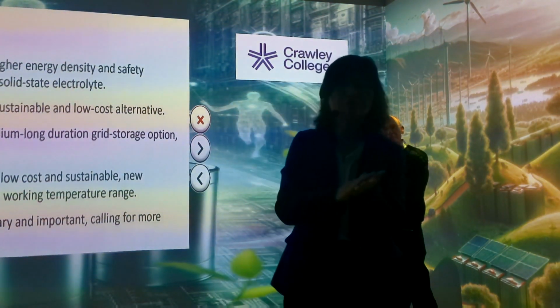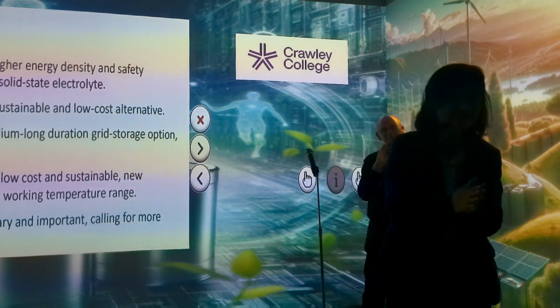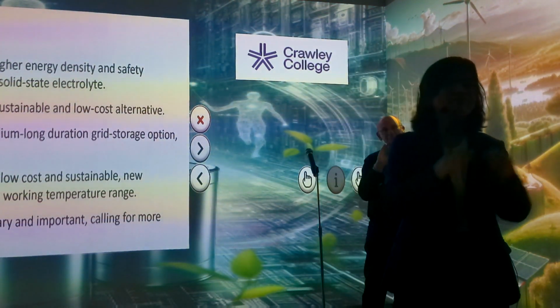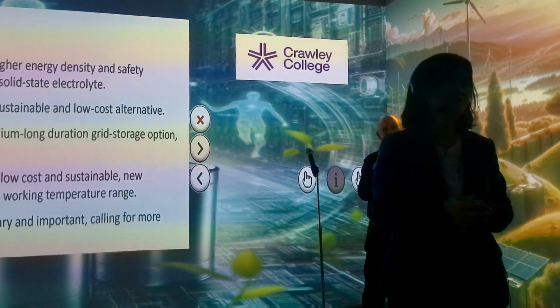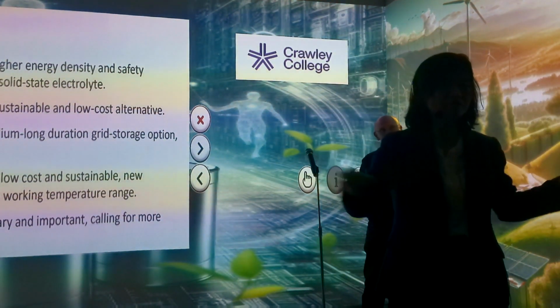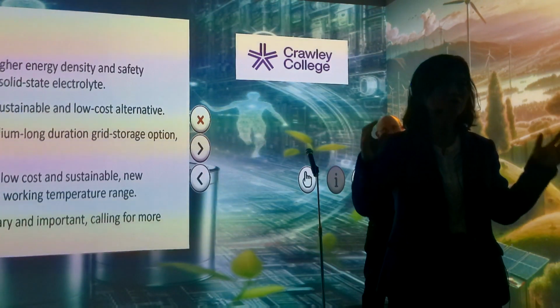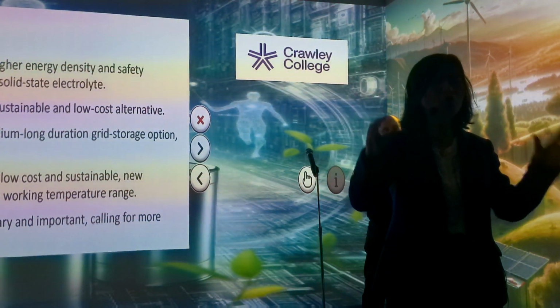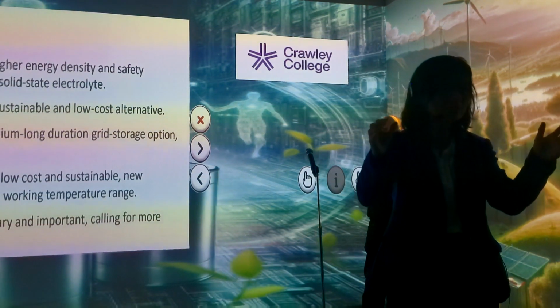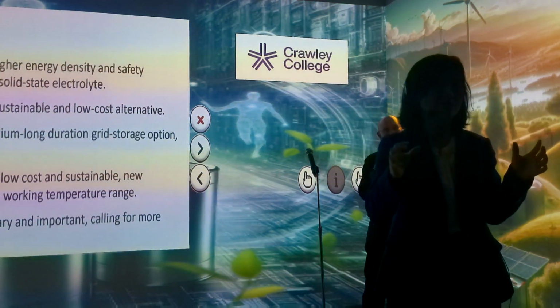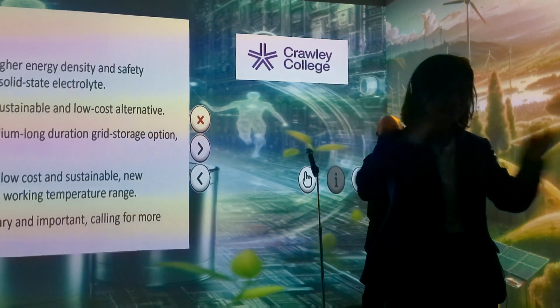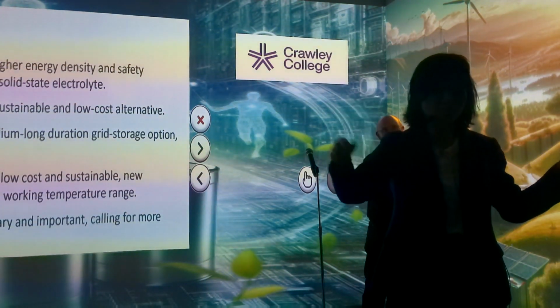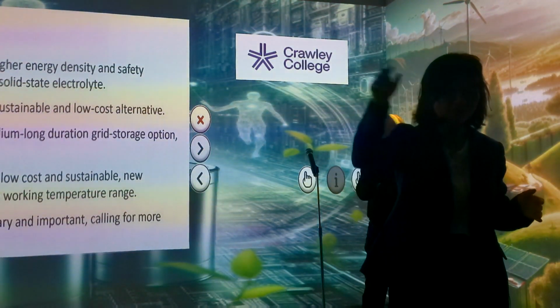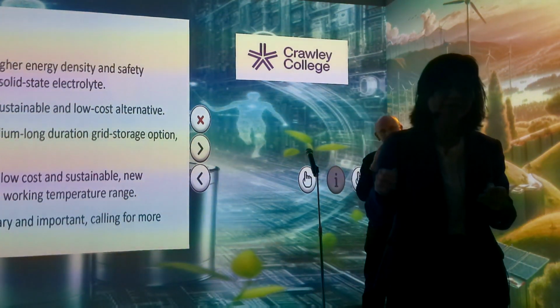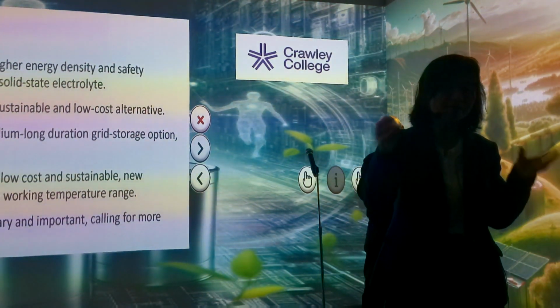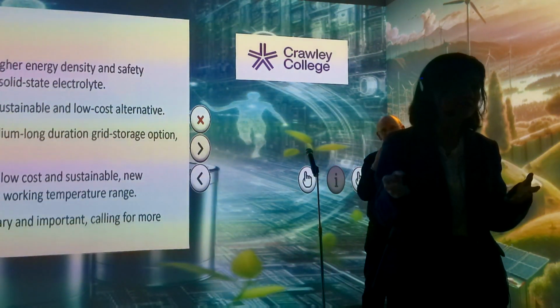Temperature increase plus oxygen release will cause problems if not properly managed - if you don't manage temperature well, if you don't limit your battery to operate only within a certain voltage window, and only charge it below 100% state of charge, then these things will happen and you will have a fire.